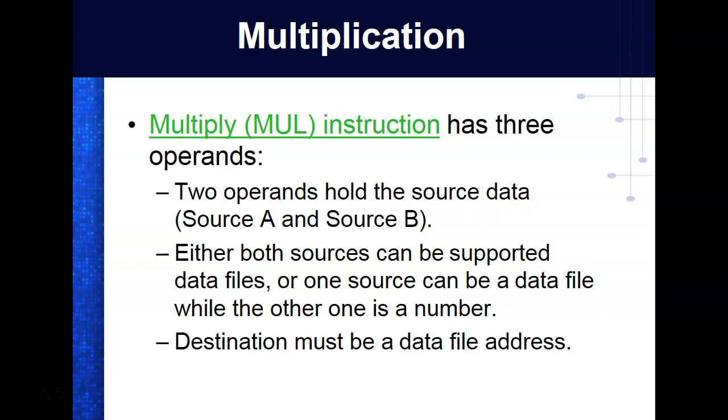So normally with our math operations, even though we can put them anywhere, normally we can use the what? We can use the N register, not register, the N data file, which the book keeps calling them. Excuse me. We could use L and we could use F. But we could actually store the results of a math operation into an output, into a 16-bit output word. And your outputs would take the state of the results of a math operation.